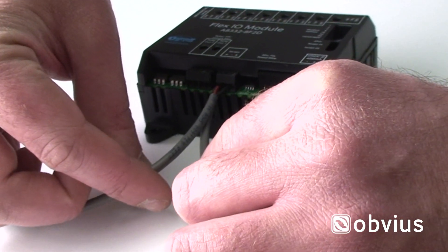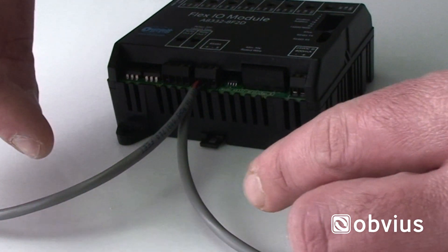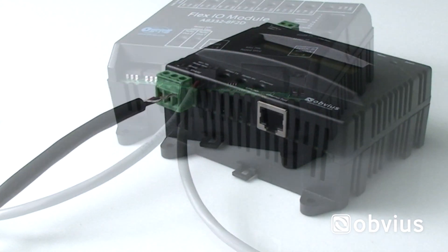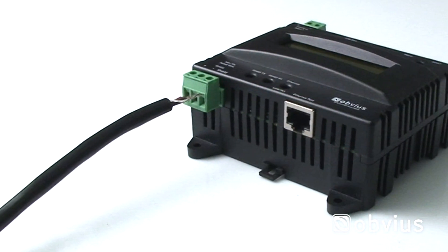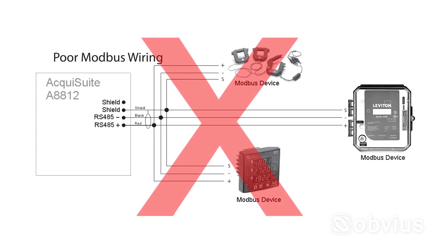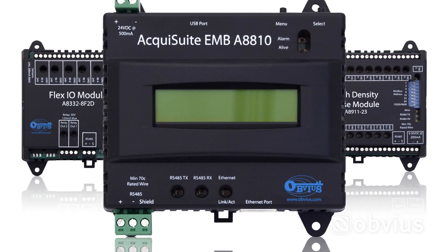To properly implement Daisy Chaining, all devices between the data acquisition server and the last device will have a double landing on each Modbus terminal. The DAS and the last device will be single land devices on each terminal. It is important to avoid having multiple termination points landing on one set of terminals. Limit all terminals to a maximum of two wires, or double landing, where the wiring is done in parallel back to the DAS.